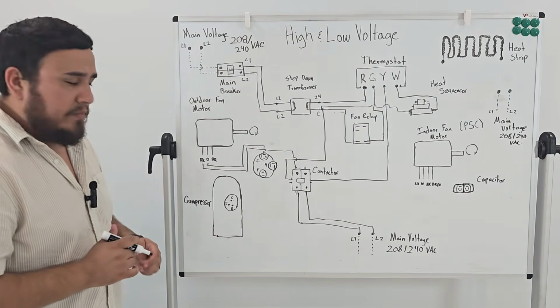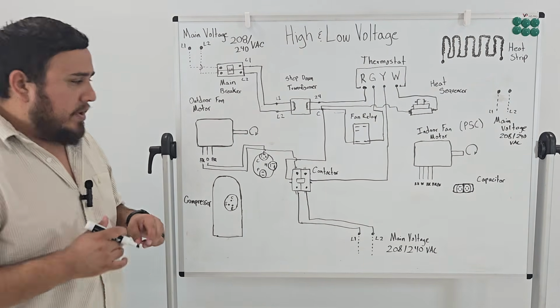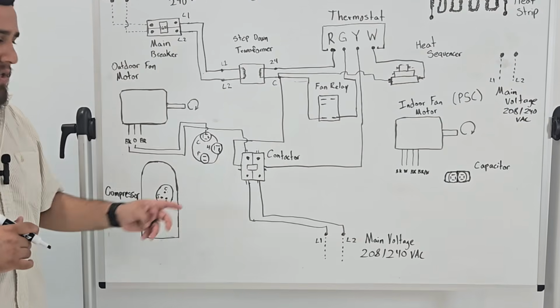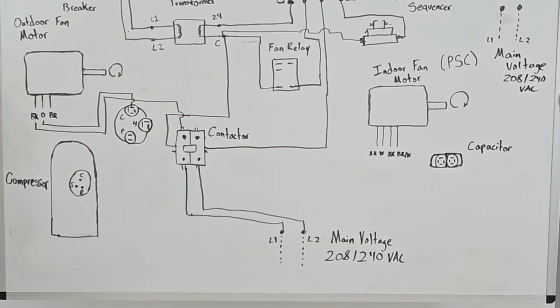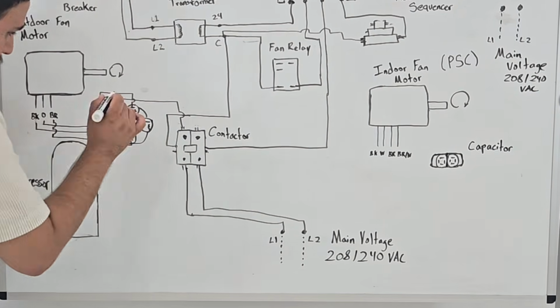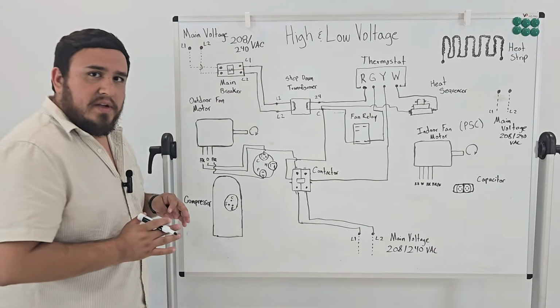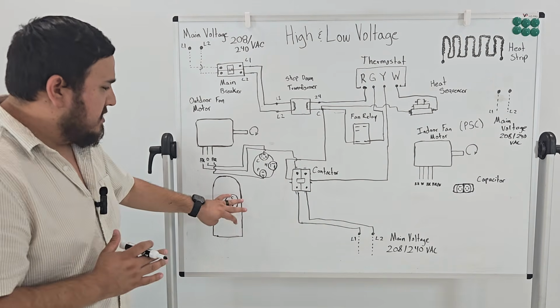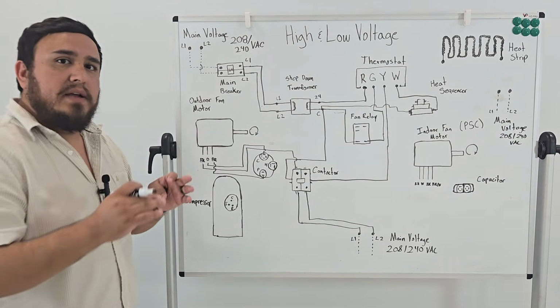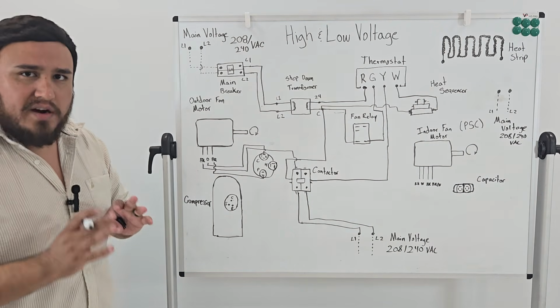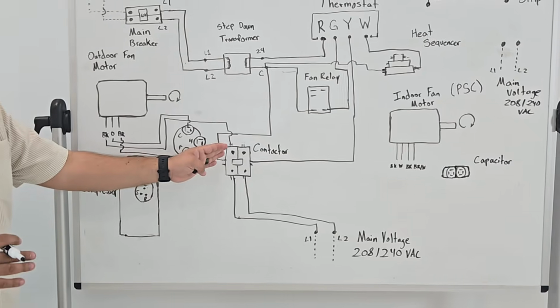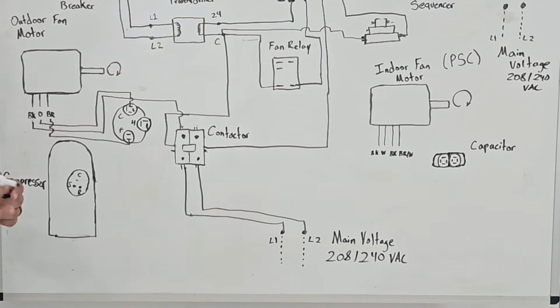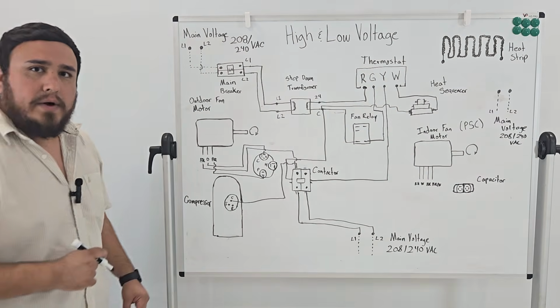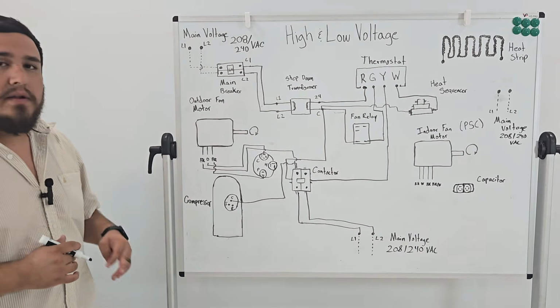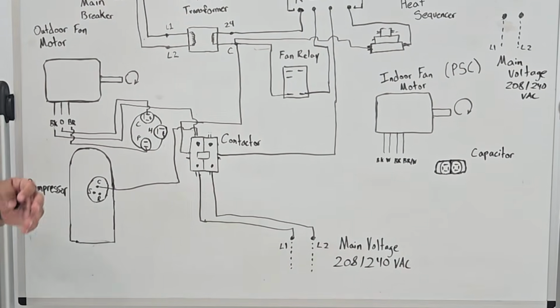All right, now the last one that I need connected is the brown wire. The brown wire is also going to go to the capacitor. That one is going to go to the F, or the fan side, of the capacitor. Let's also connect that one. So now I have finished connecting the fan motor, or the condenser fan motor. Now I'm going to focus on just the compressor alone. The compressor has a common, start, and run. So we'll focus on the common wire. The common wire is going to connect to my L1. Right, so let's do that. Let's connect the common to the L1 of my contactor. All right, now the next thing to connect is going to be the run. The run for the compressor goes to L2. Let's connect that one as well.